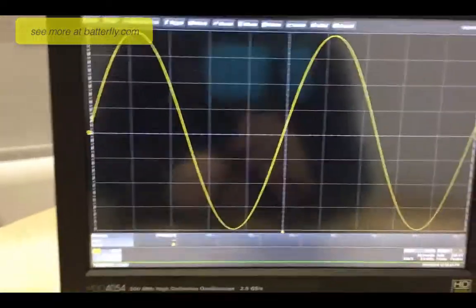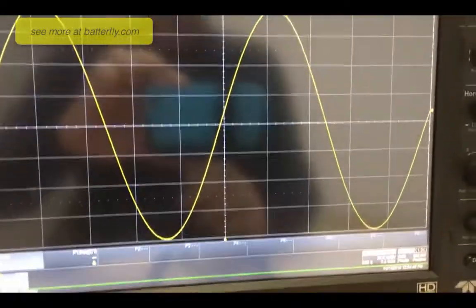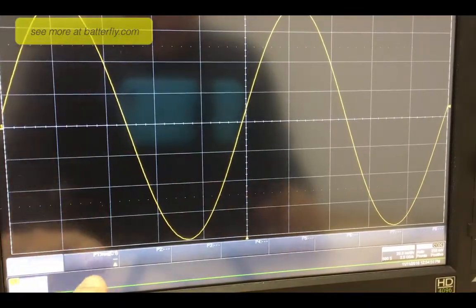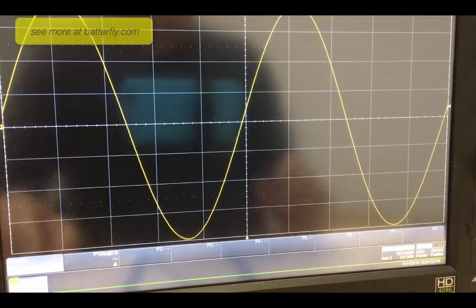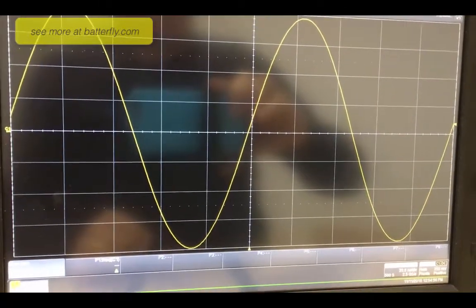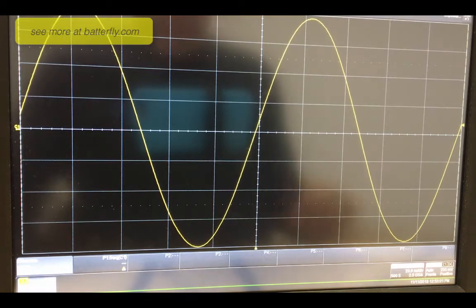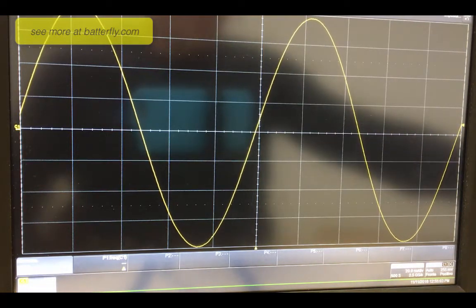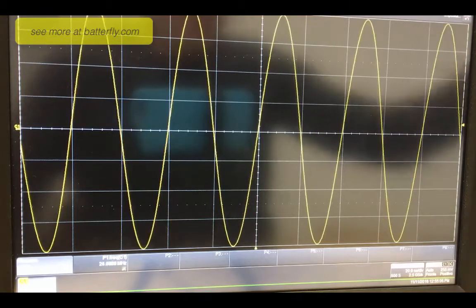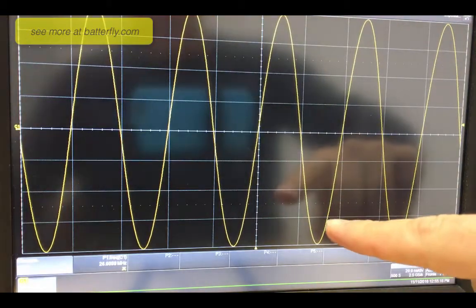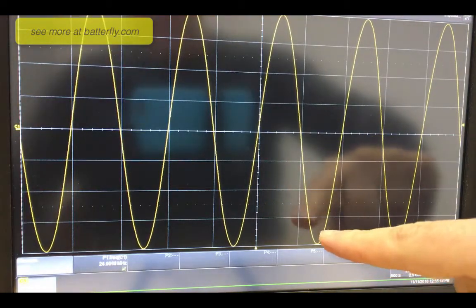Let me just put down the tripod and try to get the best of the signal. I don't know if you can see here, but later I will show you more in detail, maybe I will go closer. What I'm going to do now is input straight 25 MHz. Let's check the 25 MHz, which is in any case the limit of this generator. What I did in the scope - which is very important when you take the measurement - I put, using the fine adjustment...